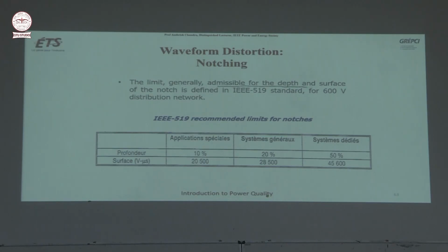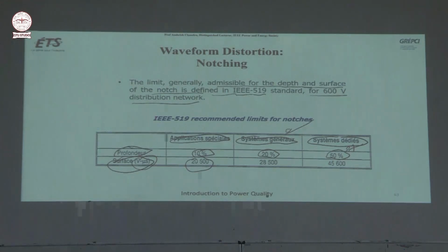The limit generally admissible for the depth and surface of the notch is defined in IEEE for 600 volt distribution network, and this is written for special applications, general and dedicated systems. So for a special application, like when you are in an airport, the limit is 10% depth, and volt-microsecond surface. For general it is increased to 20%, and for dedicated go for 50%, because there is no customer nearby, so it will not affect the other people. Allow those limits.